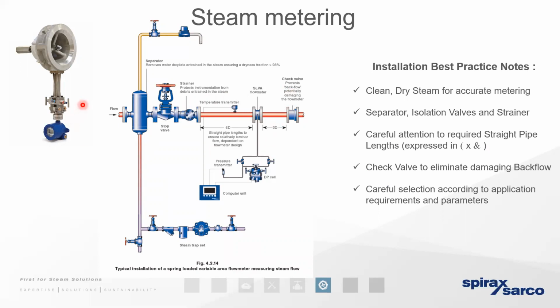So we need to take any entrained moisture away across a steam trap. We need to vent any air away for similar reasons. We need to ensure that we've got laminar flow, so we've got the correct run of pipe upstream and downstream of the meter. We want to fit a check valve to prevent any condensate from being drawn back across the meter, which could cause damage and water hammer.